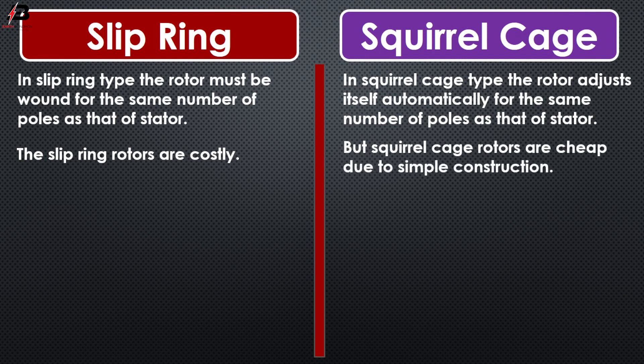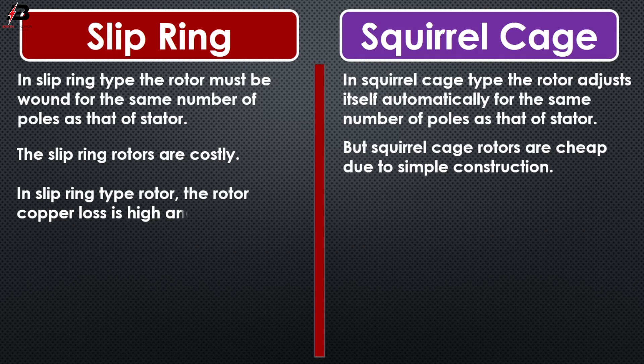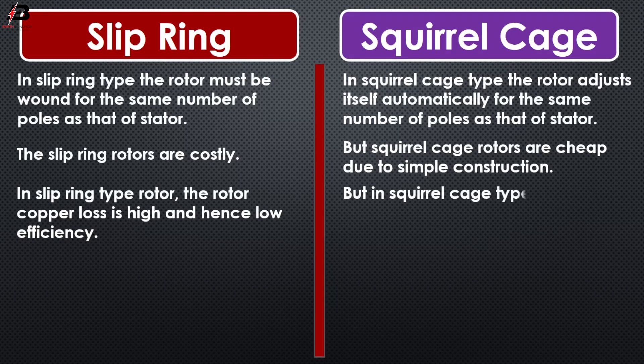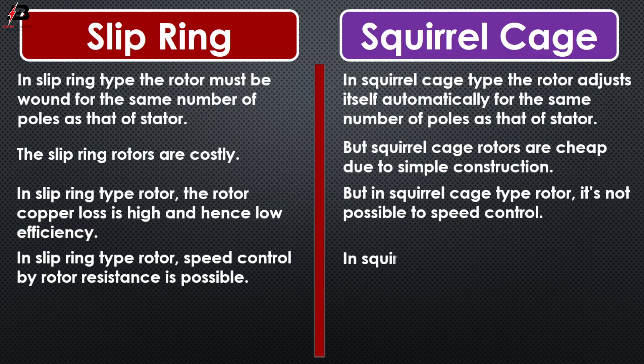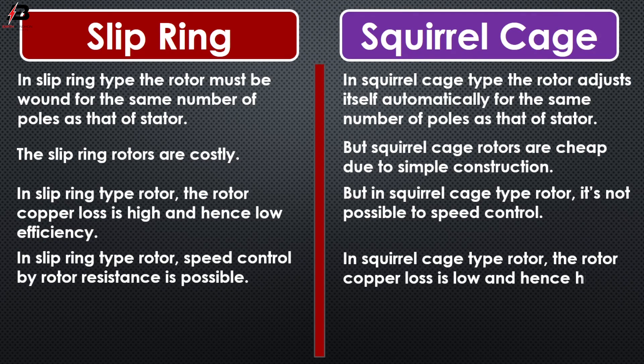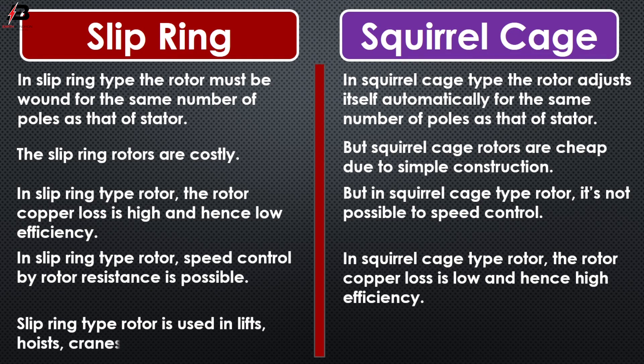In slip ring type rotor, the rotor copper loss is high and hence efficiency is low. In squirrel cage type rotor, speed control is not possible, whereas in slip ring type rotor, speed control by rotor resistance is possible. In squirrel cage type rotor, the rotor copper loss is low and hence efficiency is high.